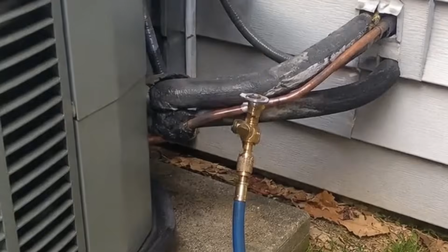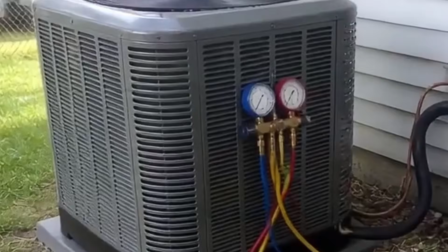And to be straight with you, peroxide is not magic. It kills biological growth, the mold and slime and algae in the wet parts of your system. That's it. It does nothing for a dead capacitor, low refrigerant, or a bad blower motor. And refrigerant work is licensed for a real reason. But that living layer is behind a shocking number of the calls and the upsells you pay for. And the rest of this list is where it hides.